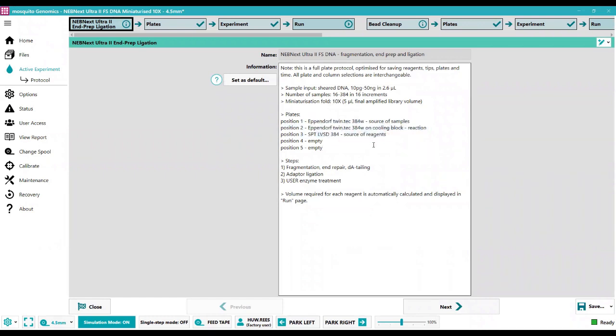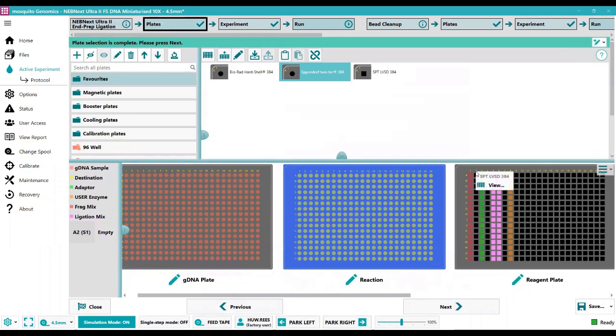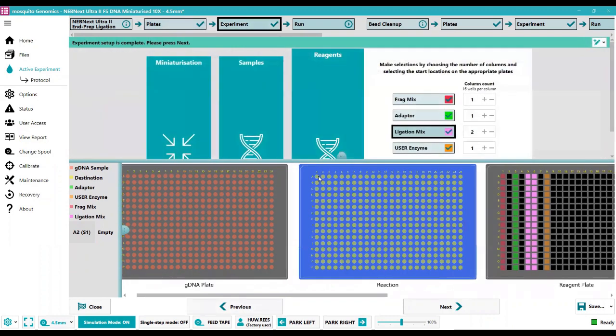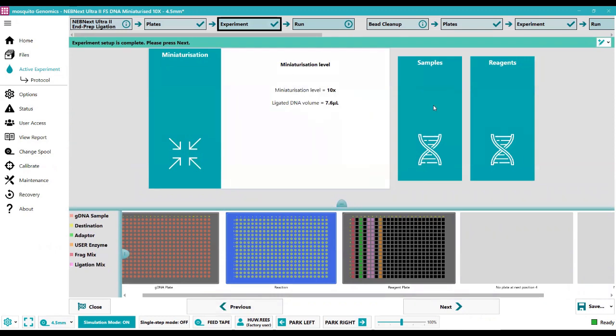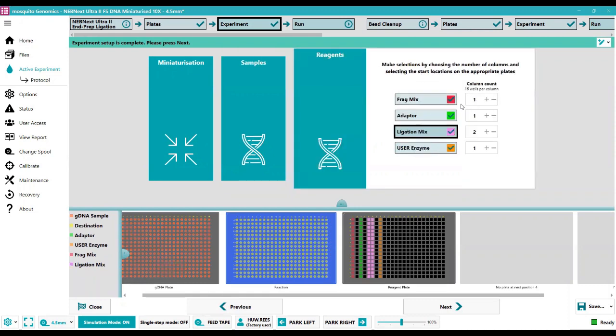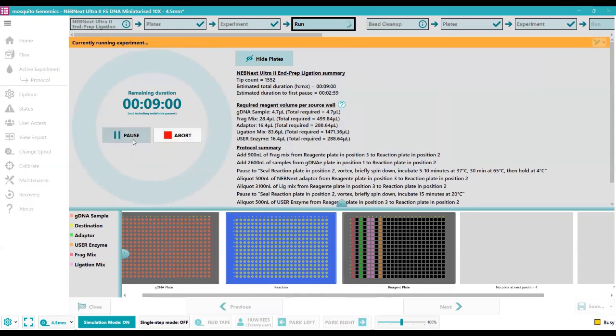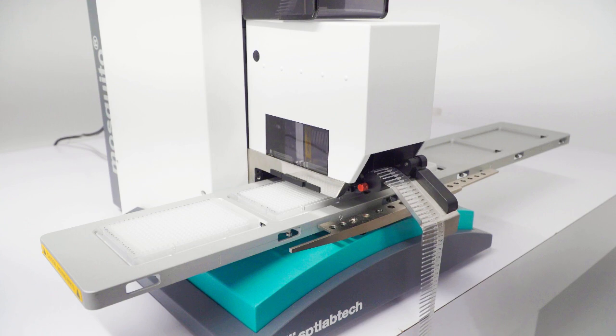The information page describes what plate types are used by default. Under the plates tab we can customize these — Eppendorf twin.tec plates on a cooling block and a low volume serial dilution plate from SPT are used by default. Under the experiment tab, the number of sample columns can be modified, and under the reagents tab we can modify reagent column positions. Then on the run tab we hit run to start the experiment. Here is the Mosquito distributing the fragmentation mix over the reaction plate.